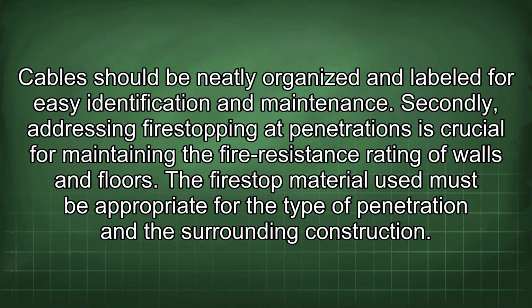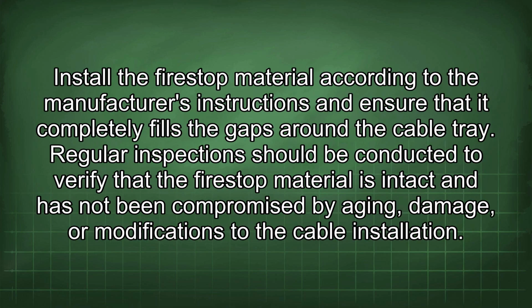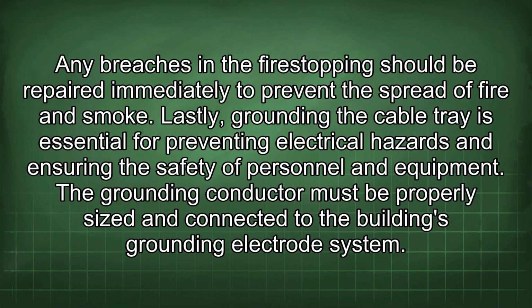Secondly, addressing fire-stopping at penetrations is crucial for maintaining the fire resistance rating of walls and floors. The fire-stop material used must be appropriate for the type of penetration and the surrounding construction. Install the fire-stop material according to the manufacturer's instructions and ensure that it completely fills the gaps around the cable tray. Regular inspections should be conducted to verify that the fire-stop material is intact and has not been compromised by aging, damage, or modifications to the cable installation. Any breaches in the fire-stopping should be repaired immediately to prevent the spread of fire and smoke.